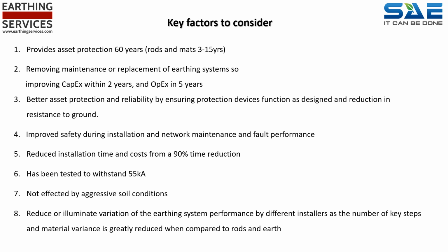It has improved safety during installation and network maintenance and fault performance, and reduced installation time and costs, from a 90% time reduction. It has been tested to withstand 55 kiloamp. It is not affected by aggressive soil conditions. It reduces or eliminates variation of the earthing system performance by different installers, as the number of key steps and material variance is greatly reduced when compared to rods and earth mats.